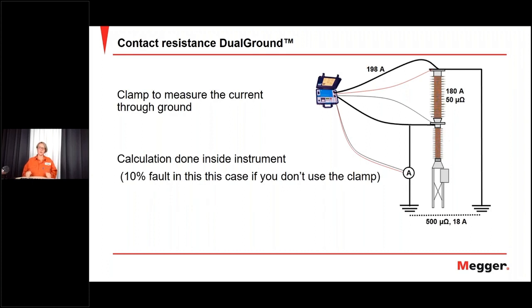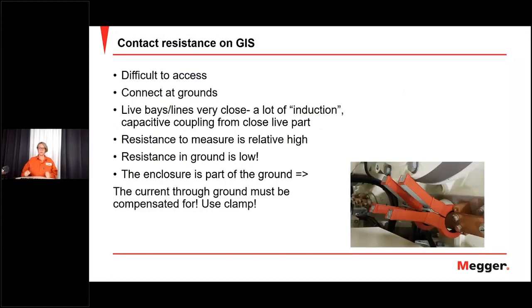We're using the Mjolnir here in this picture. We compensate automatically by using a clamp in the ground. But when you measure on GIS, then the resistance in the ground is really, really low. And it's always also very difficult to access. You can't connect directly at the breaker's contacts. You normally need to connect far away from the breaker, maybe at ground. And you also have problems where you really want dual ground, because you have a lot of induction, capacitive coupling from close live parts, because it's much more tight and narrow.